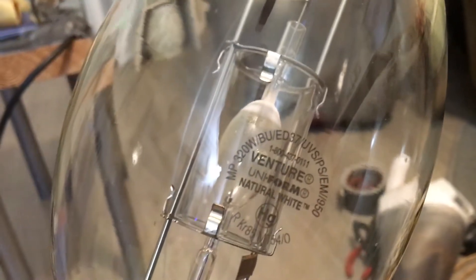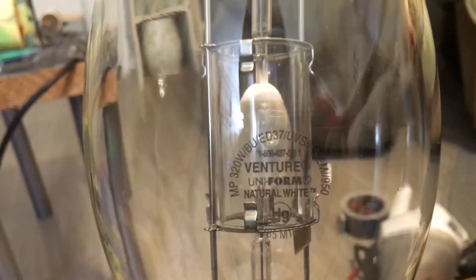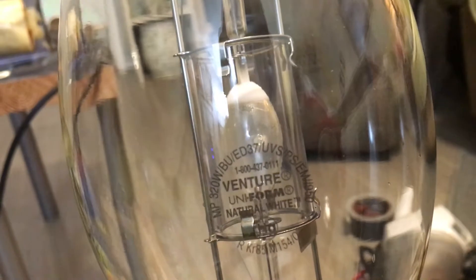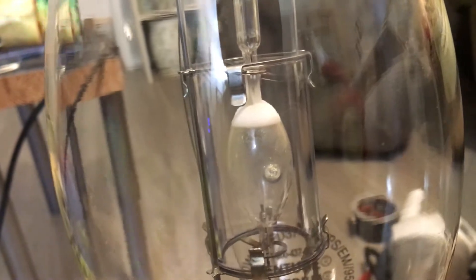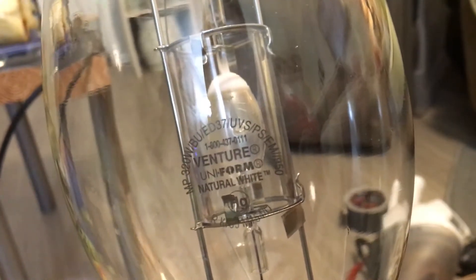After that we have our operating position for the arc tube which is base up plus or minus 15 degrees. Then our bulb shape altogether — it's the elongated dimple 37 bulb, ED37. And we have our shield type which is UV shielded, so this has a shield that can absorb most of the UV radiation from the arc tube. And then our starting method, which is pulse start — the PS meaning pulse start, the EM means this bulb is only supposed to be used on electromagnetic coiled ballasts.